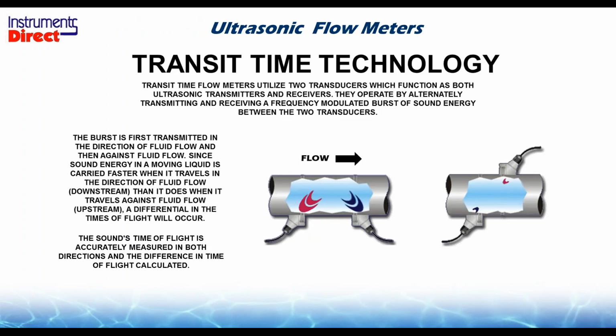So if we use the same concept on a pipe, the man in the river is more the picture to the right here. We send a sound burst across the pipe to this other sensor. It's going with the flow. It'll take a certain period of time to get from here to here. But at the same time, we're going to send a sound burst from this sensor back across the pipe, going against the flow. It will take a longer period of time. The differential between the two transit times is how we calculate how fast the flow is going inside the pipe, not a river here.